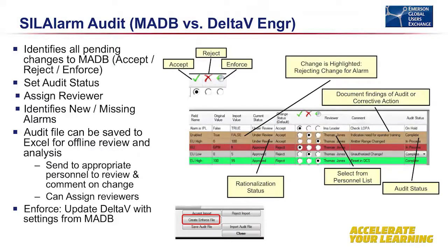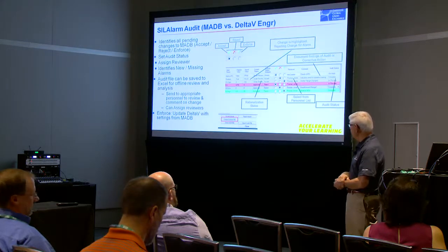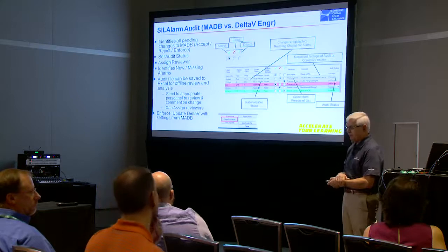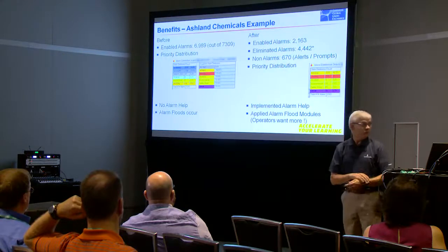Within the SIL alarm product, there is likewise an ability to not only bulk deliver into the Delta V system the desired alarm settings, but also to bulk export out of Delta V and bring into SIL alarm the as-configured alarm settings to be compared against what the master alarm database says, with tools that would allow you to review, accept, or reject the changes that you see between the configured system and the master alarm database. So a lot of good capability right there. It also allows you to create an enforce file that you could actually transfer back into the Delta V system to reestablish changes that were made in the engineering system. So I think that one, back to you, Todd.